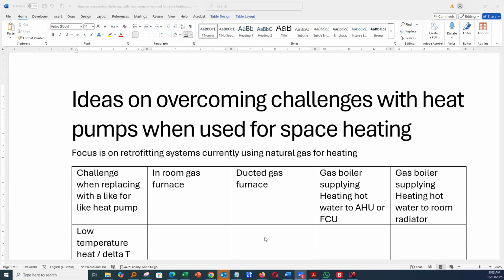Ducted gas furnace, well, then you may be running hotter temperatures because you're relying on mixing of the air. But again, I think you could probably use a split system to replace a ducted gas furnace. Okay, gas boiler supplying heating water. Now, this is a problem. Typically, heating hot water is supplied at 75 to 80 degrees Celsius. A standard heat pump is going to be producing about 45 degrees Celsius, maybe 50. So there's a big difference there. And because of the lower temperature, you're not going to generate as much useful heat from that fan coil. So that's a problem. Heating hot water to a radiator, typically radiators are supplied with pretty hot water as well, and that could be a problem as well.